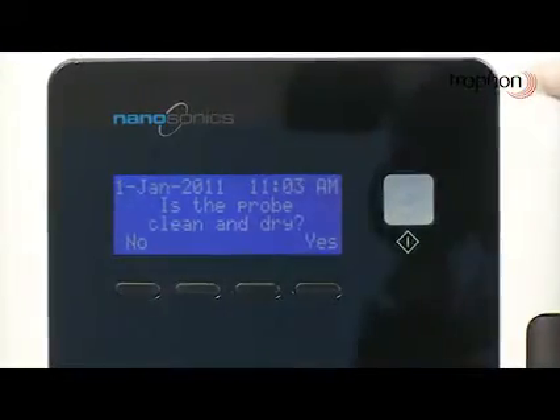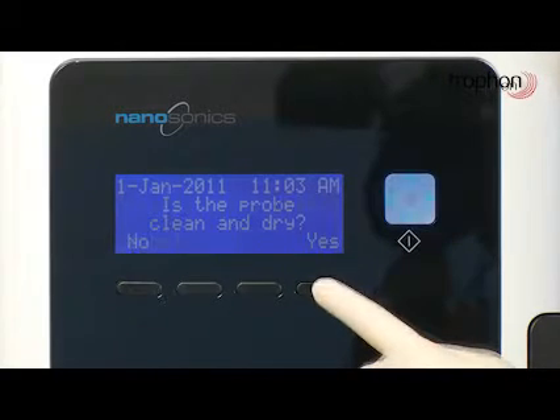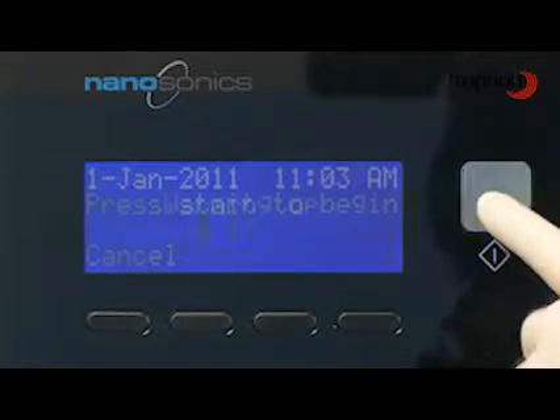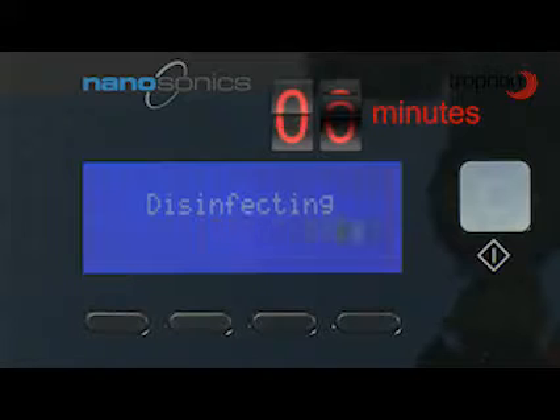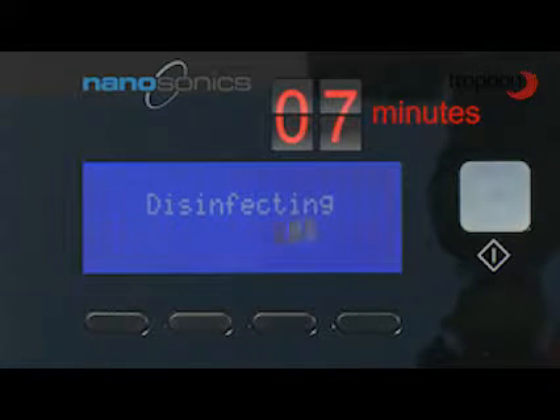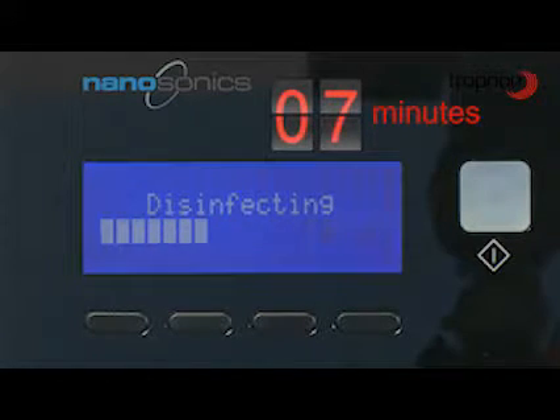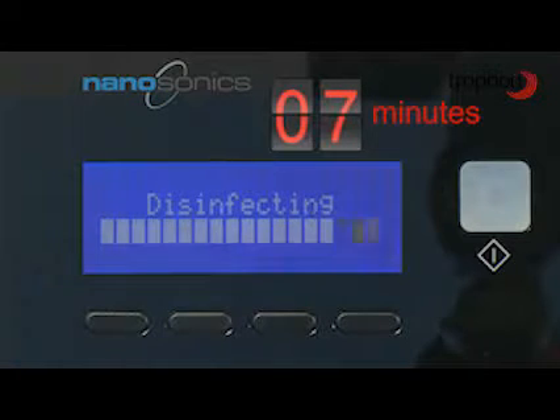To start the disinfection cycle, you must close the chamber door. Select Yes to confirm that the probe is clean and dry. Press Start to begin. After 7 minutes, an alarm will sound, and the screen message will read Cycle Complete, confirming a successful disinfection cycle.